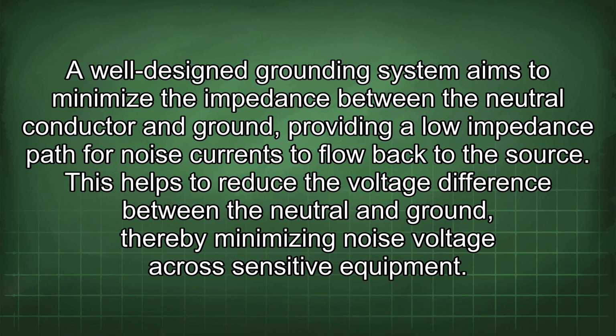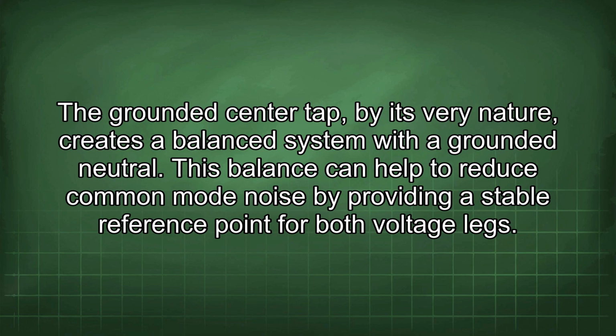A well-designed grounding system aims to minimize the impedance between the neutral conductor and ground, providing a low impedance path for noise currents to flow back to the source. This helps to reduce the voltage difference between the neutral and ground, thereby minimizing noise voltage across sensitive equipment. The grounded center tap, by its very nature, creates a balanced system with a grounded neutral. This balance can help to reduce common mode noise by providing a stable reference point for both voltage legs.